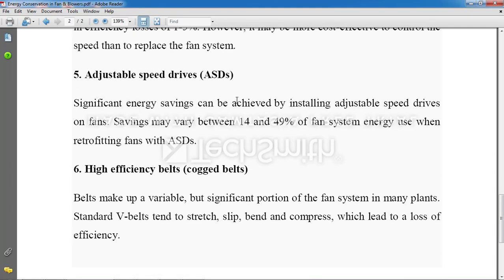The next point is adjustable speed drive. We had already discussed variable speed drives, and we have taken the example of the ceiling fan regulator as the best example of how we can control the speed according to our convenience. In big industries where heating is quite high, they put exhaust fans, and according to the heat generated inside the system the speed of the fan gets adjusted. If the process inside the system is half loaded, the exhaust fan speed should be at moderate speed. But whenever the system is fully loaded, the fan should rotate at the highest speed to exhaust the heated air from the inner system to the outer system.